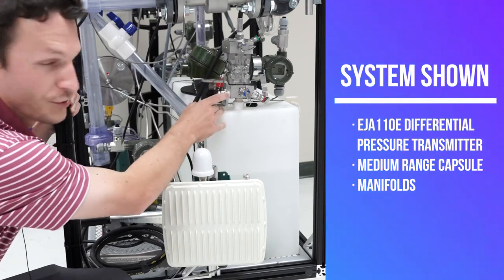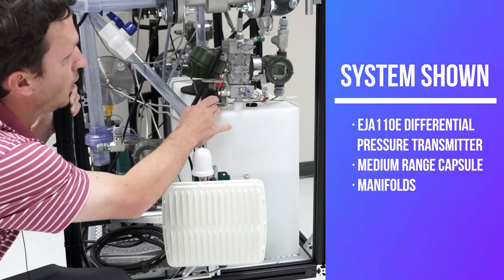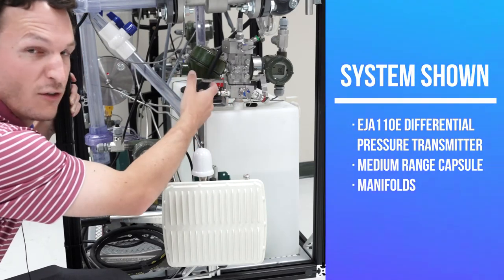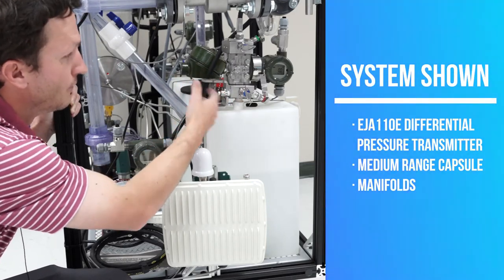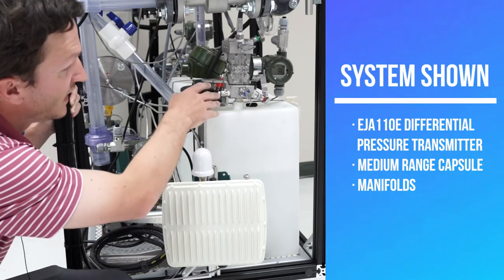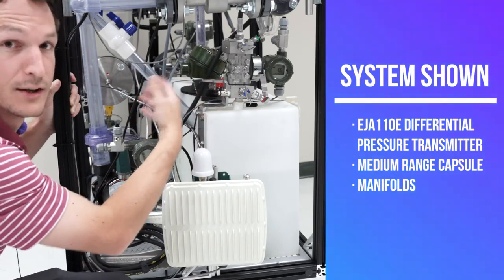We can charge one side of the transmitter, the low side, with high pressure to simulate an overpressure incident, and then I can vent it and bring it back to a steady state where it is right now, creating zero differential pressure.